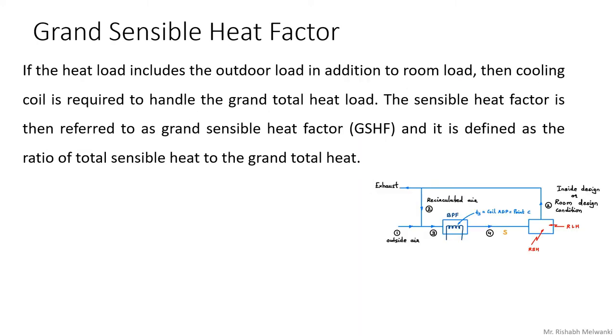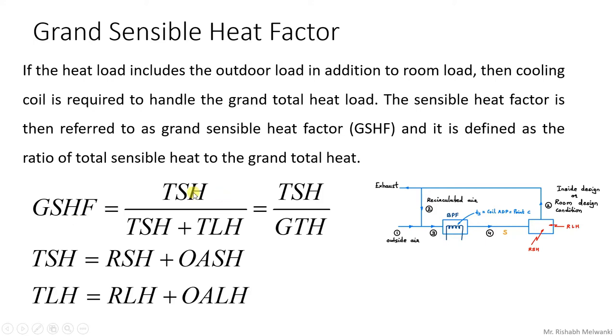The grand sensible heat factor (GSHF) accounts for both the room load and the outdoor air load on the cooling coil. If the heat load includes the outdoor load in addition to the room load, the cooling coil must handle the grand total heat. GSHF is defined as total sensible heat divided by grand total heat, where grand total heat equals total sensible heat plus total latent heat. Total sensible heat is room sensible heat plus outside air sensible heat, and total latent heat is room latent heat plus outside air latent heat.